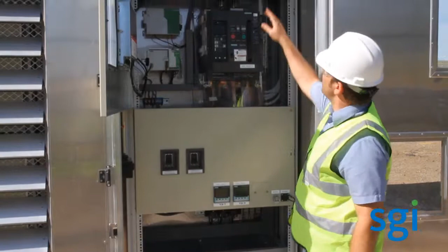Okay. So you have the primary power that comes in from the top into this main disconnect or main breaker. So this main breaker actually feeds, as I mentioned, the 2 primary disconnects for the bus bars that are feeding the racks in an A and a B fashion. So this customer has a single source of power. Again, if they wanted redundant power, they would have two disconnects here. 2 separate disconnects and something we call an ATS, but I won't go into that at this point. So you have a single primary disconnect, and you have the 2 disconnects for each one of the bus bars.